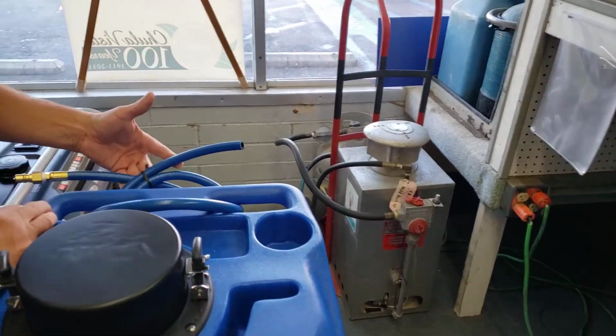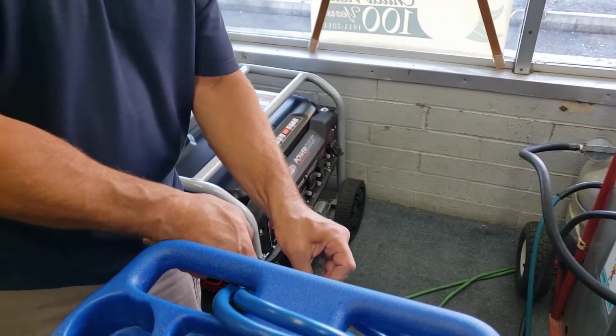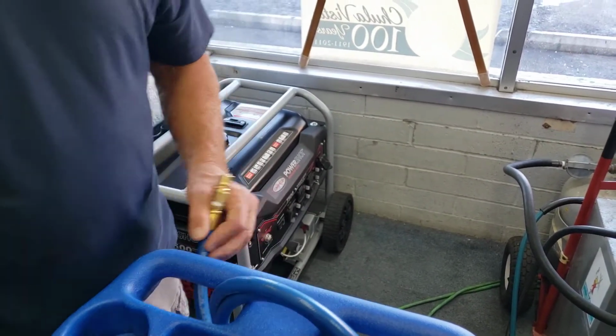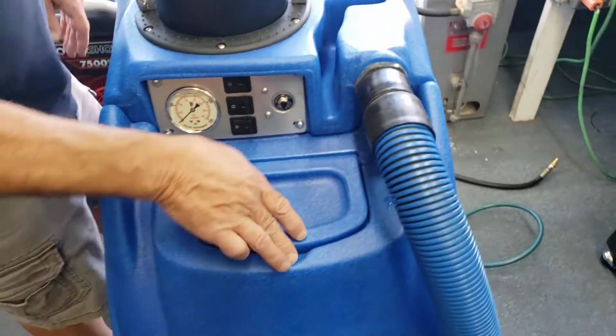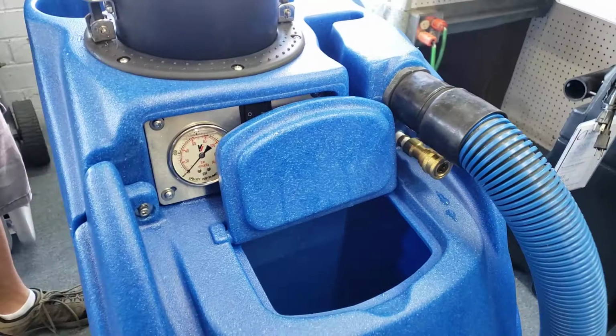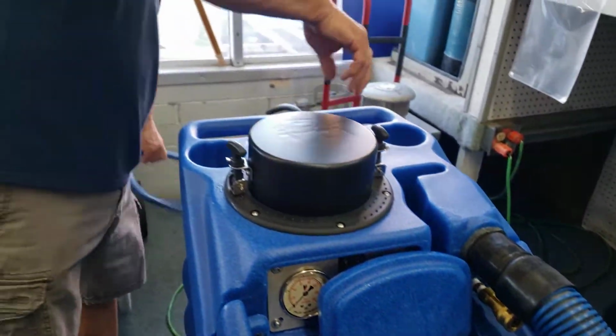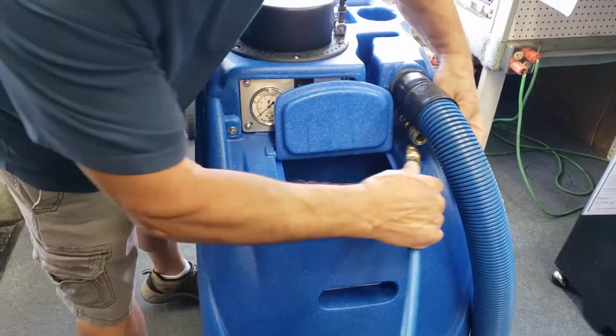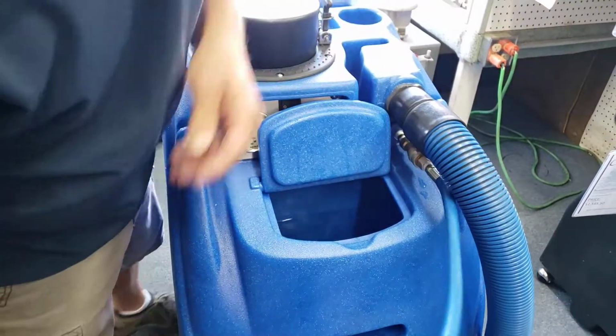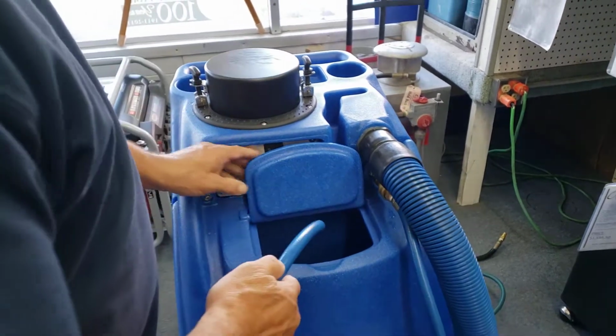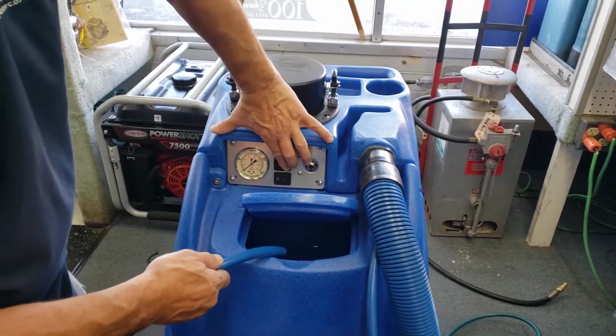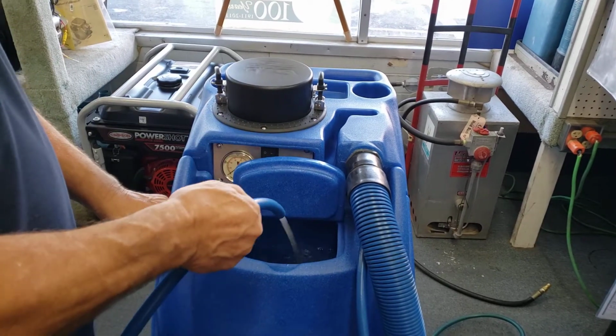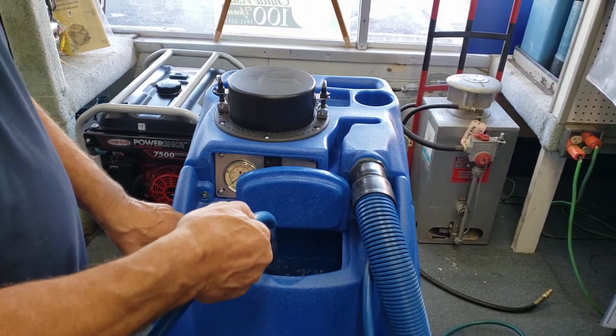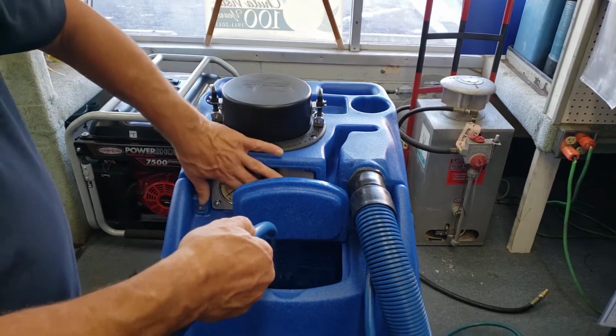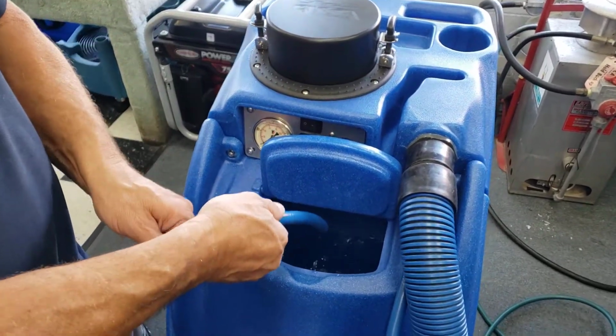Each machine comes with a bleeder hose, which is zip tied on. This bleeder hose is designed to be hooked to the front of the unit right here, and then you can open up the hose. Let me just break this. Like so. And then you can turn your pump on and eliminate any air that might be in the system. As you see, it first comes out a little airy, then it goes completely clear. At that point, you know you've gotten all of the air bubbles out of the system.